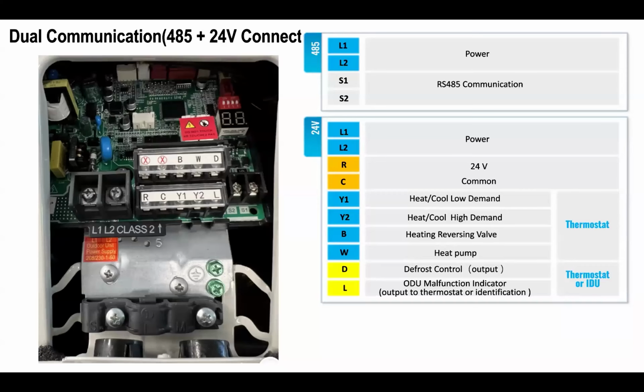D is the defrost output. So if you're using full 24 volt control, D replaces your W back in, that's for your auxiliary heat for defrosting. So you send that back in, you put it on W1 or W2, and that's your defrost heat, if you're using auxiliary heat for defrosting. You don't have to do that with ours, because when ours goes into defrost, the indoor blower shuts off. So it doesn't blow cool air in the house while it's in defrost.